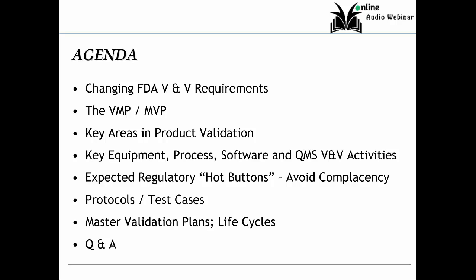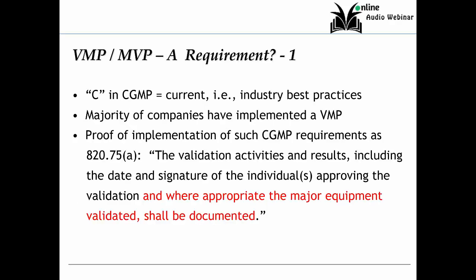Now, we'll use the example of the IQ, OQ, PQ, but you're not held to that. You can use other terminology, but you have to cover the areas that would be addressed by IQ, OQ, PQ. We'll define the terms and what would be typical of the type of test cases under each one of those three key qualification areas. And then we'll talk about life cycle, cradle to grave issues as we go through this discussion. So as I mentioned, the C in cGMP means what's current. In other words, industry best practices.